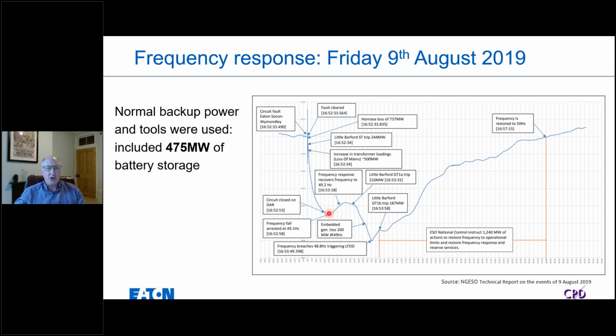And with those actions, we see the frequency start to rise. They start to restore the system to within, coming more towards within tolerance. But then we start to see another generator trip. That then has consequential trips as we start to see that frequency reduce, and we start to see embedded generation tripping. We start to see larger generators tripping because we're going below those low frequency grid set point limits as dictated by G98 and G99. And the frequency drops all the way to this point here.